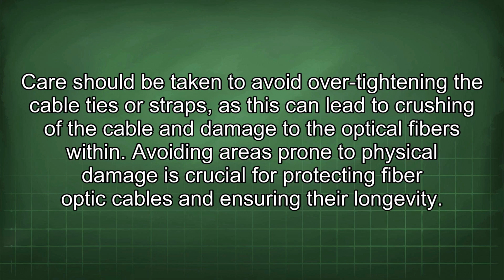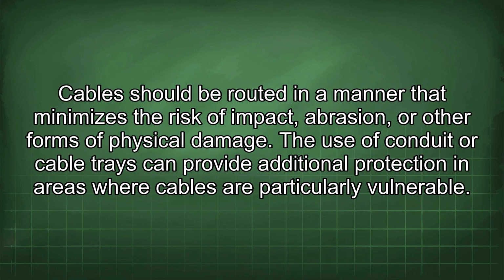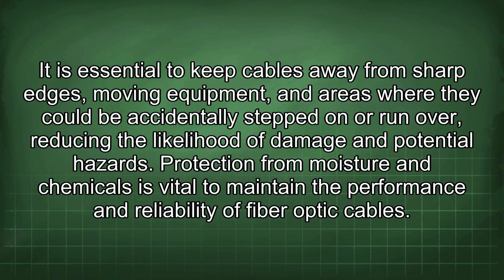Avoiding areas prone to physical damage is crucial for protecting fiber optic cables and ensuring their longevity. Cables should be routed in a manner that minimizes the risk of impact, abrasion, or other forms of physical damage. The use of conduit or cable trays can provide additional protection in areas where cables are particularly vulnerable. It is essential to keep cables away from sharp edges, moving equipment, and areas where they could be accidentally stepped on or run over, reducing the likelihood of damage and potential hazards.